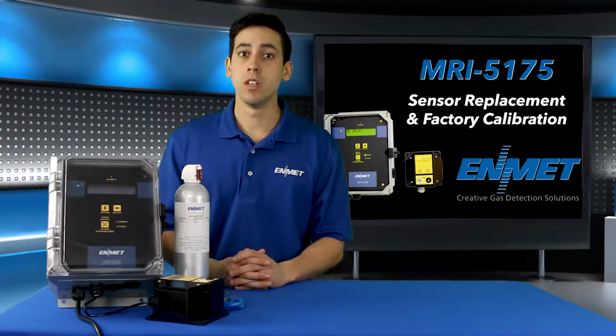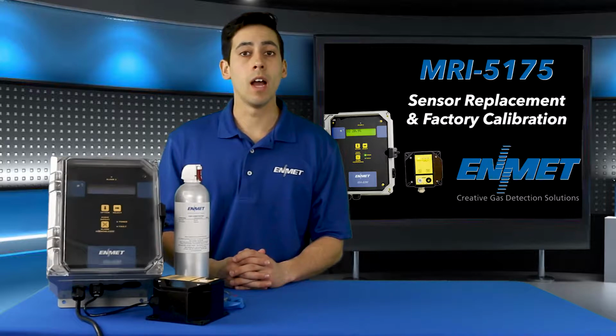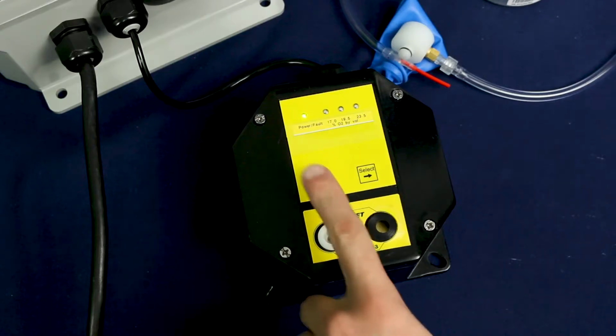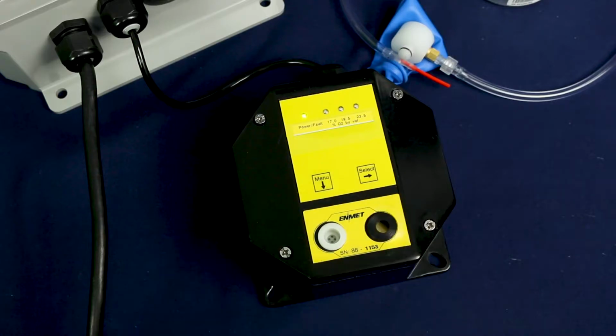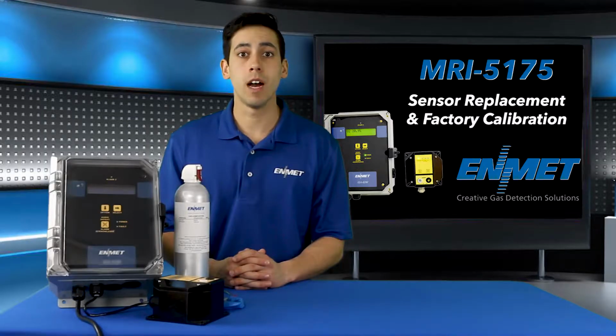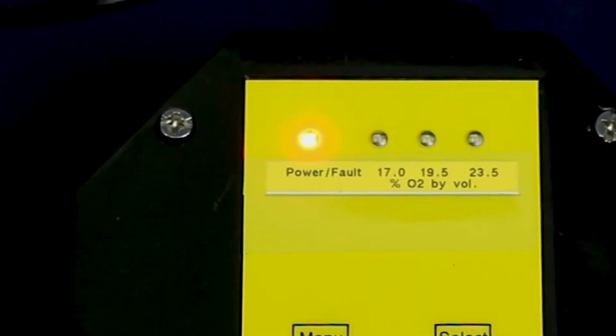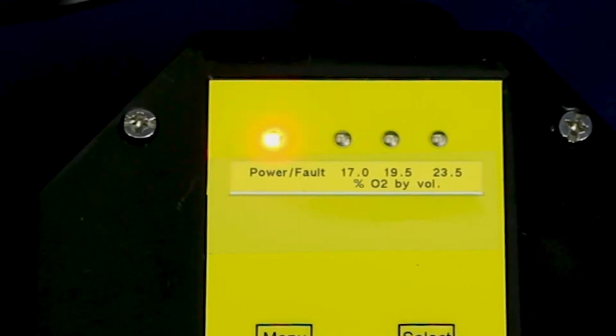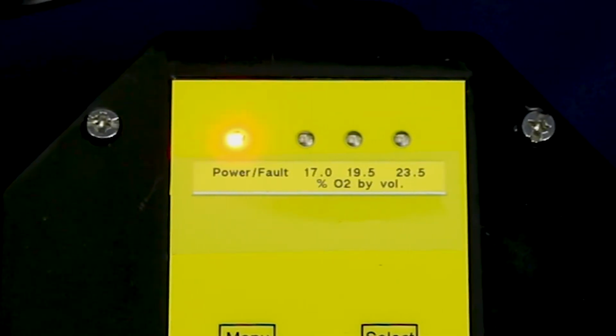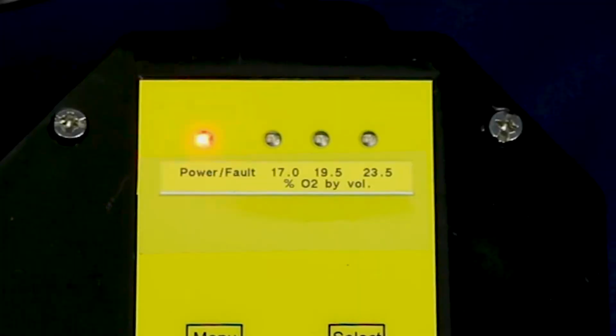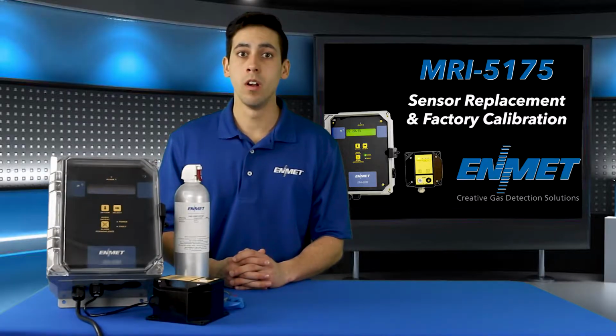The calibration is performed at the MRI 5175 remote sensor transmitter. The calibration functions are operated through the menu and the select switches. The MRI 5175's output is communicated via the power fault LED blink sequences. Consult your MRI 5175 manual for the table of LED sequences.